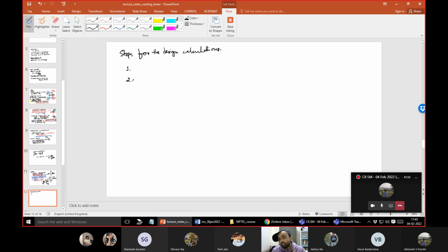And this should be obtained based on the weather data of that geographical location where this cooling tower will be installed, right? And this wet bulb temperature actually determines the approach, right? And you have to maintain a certain level of this approach, and this wet bulb temperature is the highest during the rainy season possibly, right?